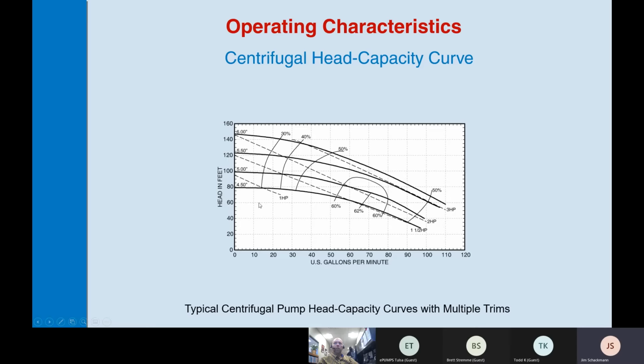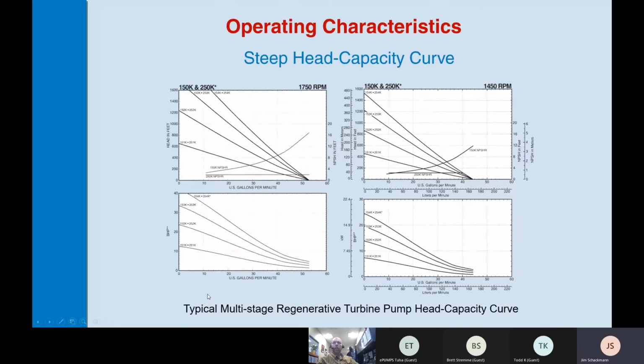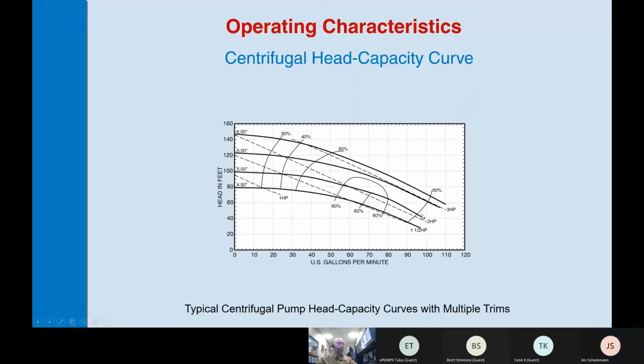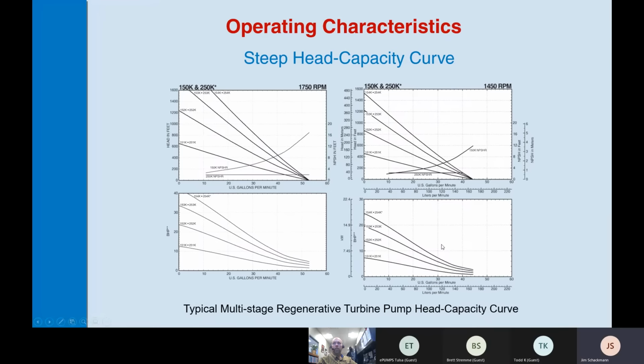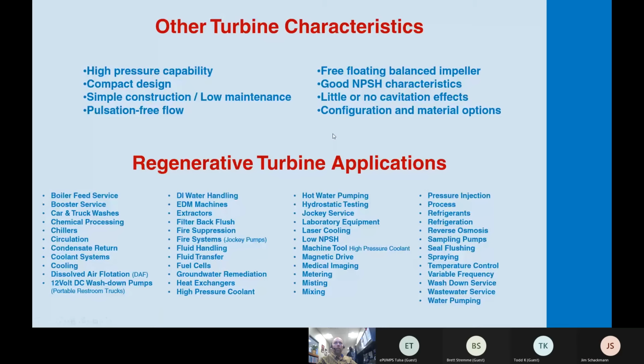Sure. And so here's a typical centrifugal pump. As you can see, the centrifugal pump doesn't hit nearly the high pressure that the regen turbine pump did. But the flow goes out much further, because centrifugal pumps are known for their flow, where regen turbines are known for their pressure. And that's where the applications come in for what you would use the regen turbines for, which we'll go over in a minute.